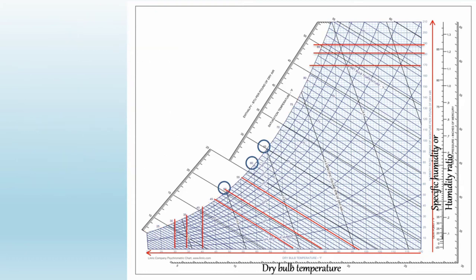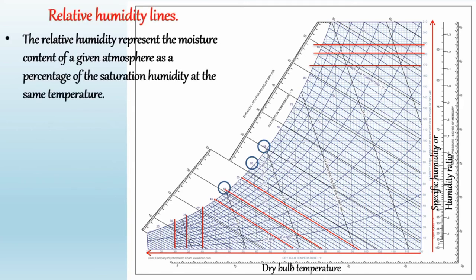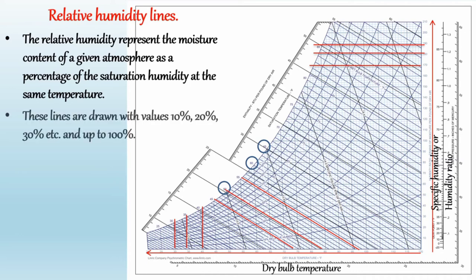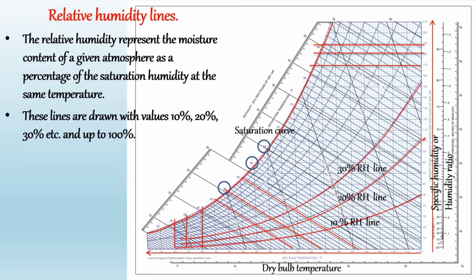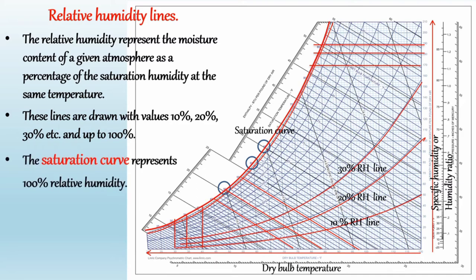The next line is the relative humidity line. Relative humidity represents the moisture content of a given atmosphere as a percentage of the saturation humidity at the same temperature. In the psychrometric chart, curved lines show the relative humidity lines. These lines are drawn with values such as 10%, 20%, 30%, up to 100% relative humidity. The 100% relative humidity line represents the saturation curve. The values of relative humidity lines are given along the lines.